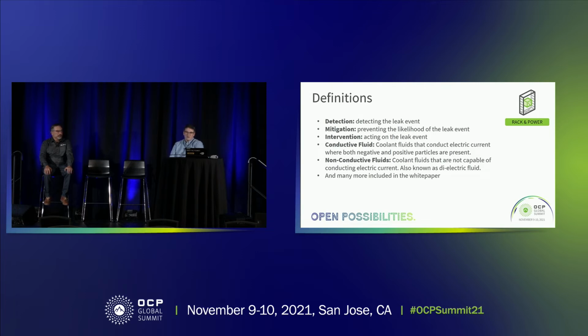The difference, as we mentioned before, we boiled down into two things: a conductive fluid or medium, and a non-conductive fluid or medium. Typically your conductive fluid is a water-based coolant. You can use direct conductive sensors to detect that. A non-conductive one, we refer to in the paper as dielectric, but it does include refrigerants. That's definitely a non-conductive leak that has various different issues to factor in.